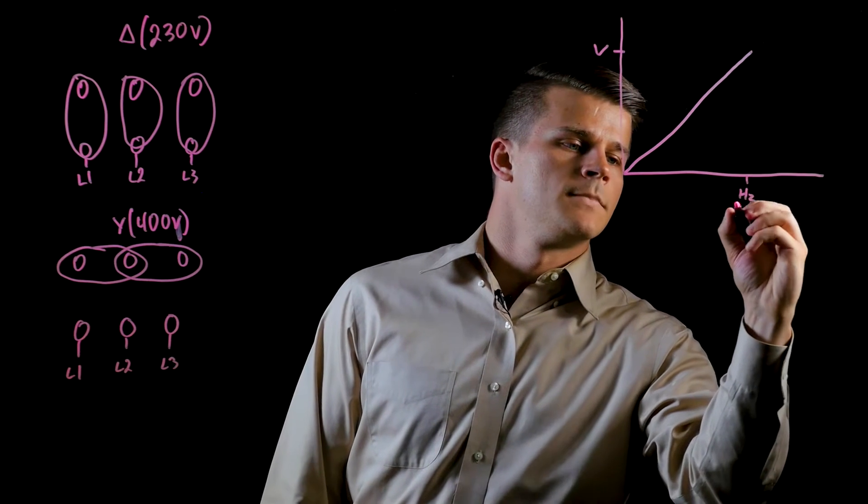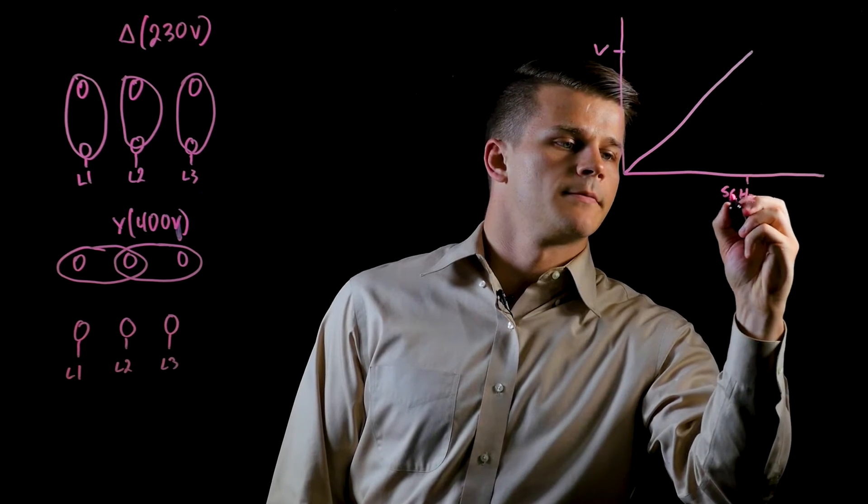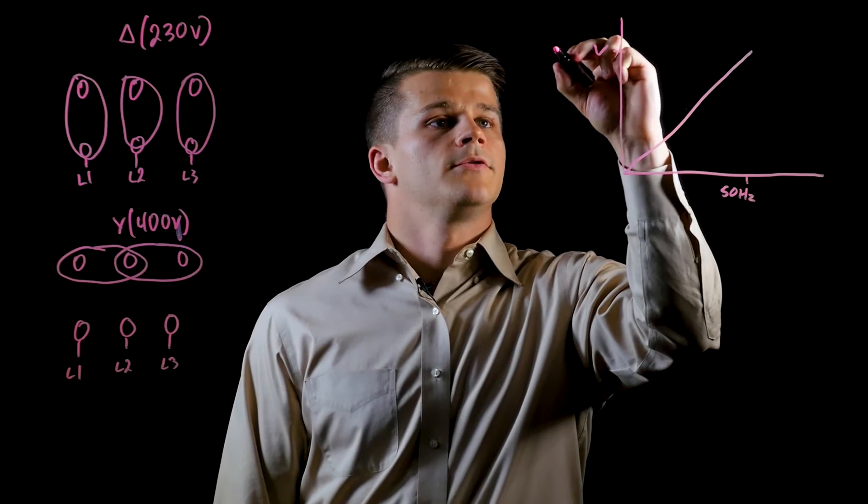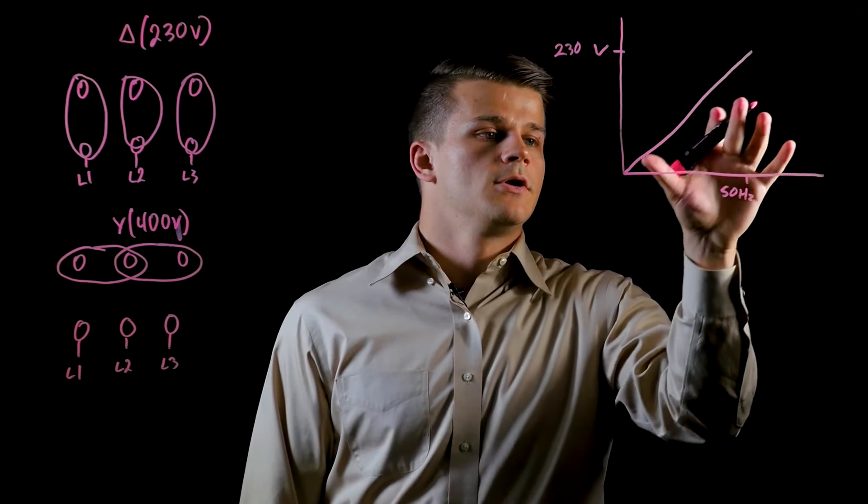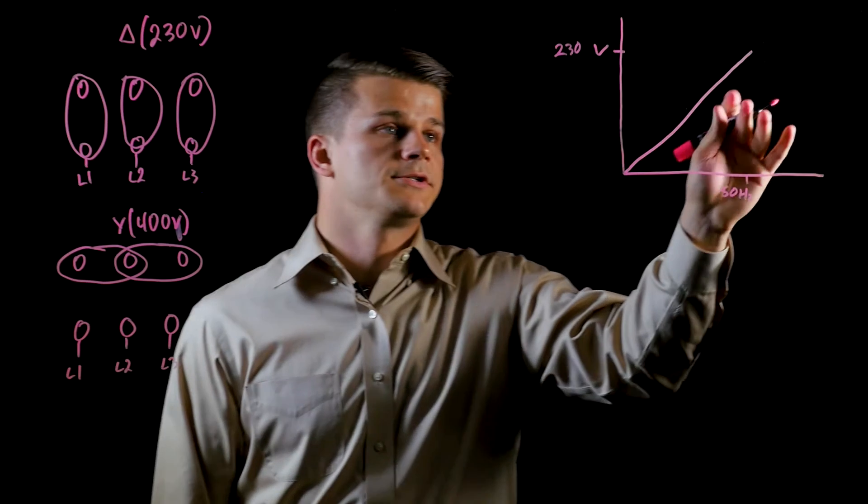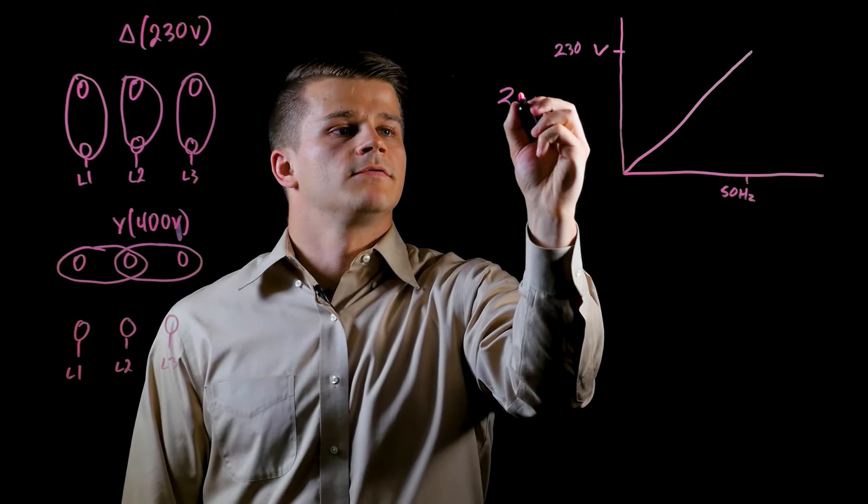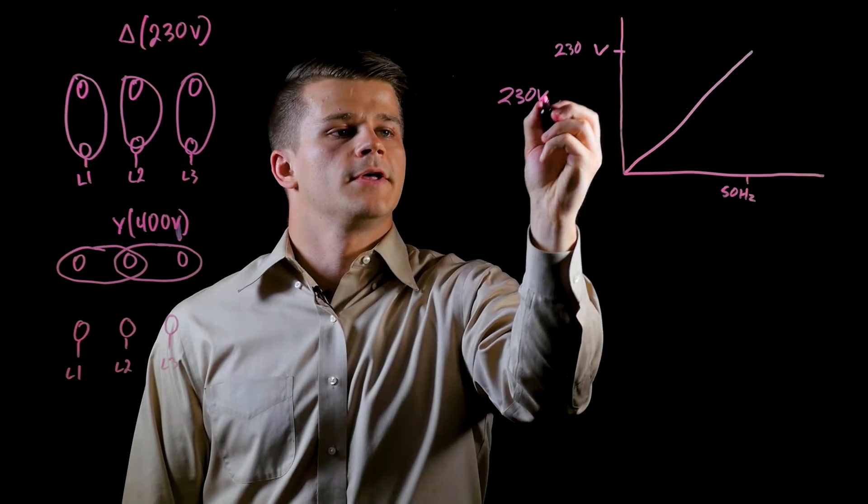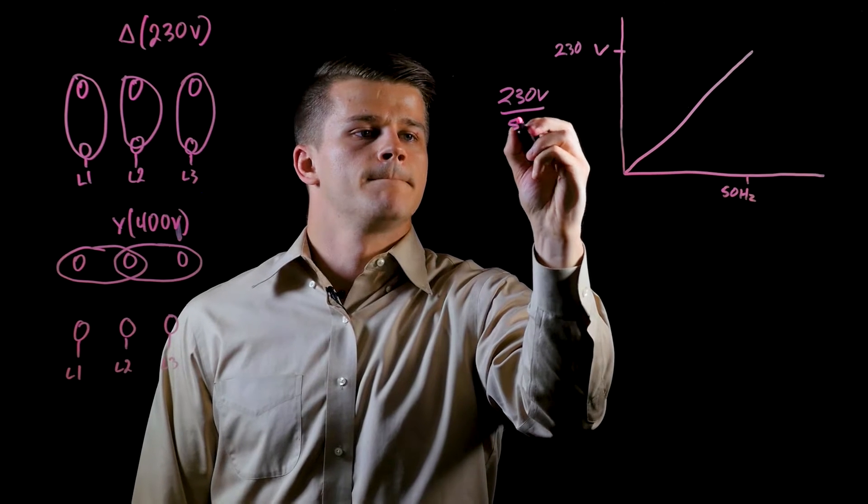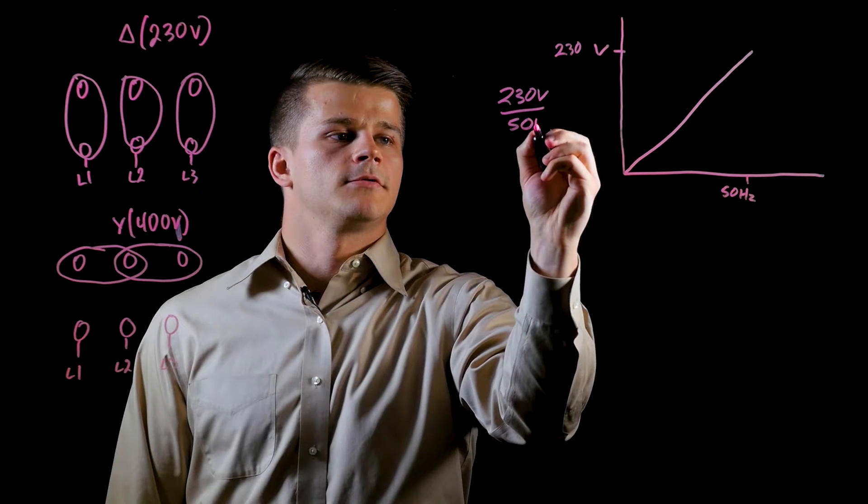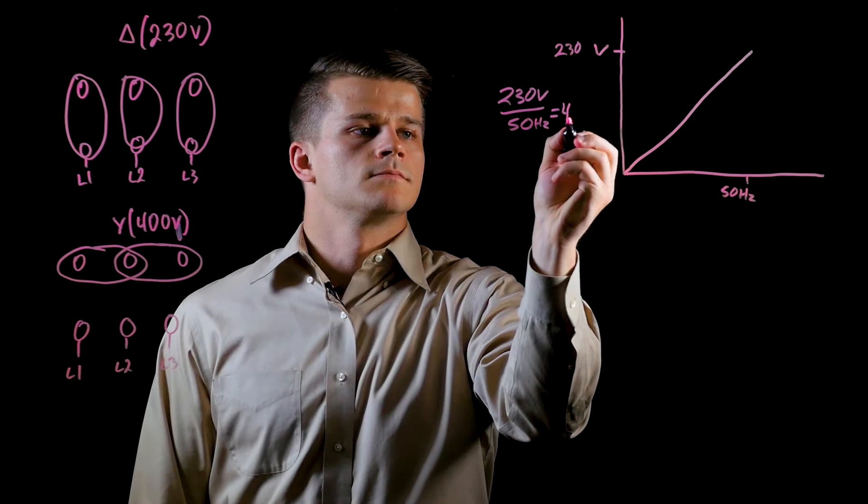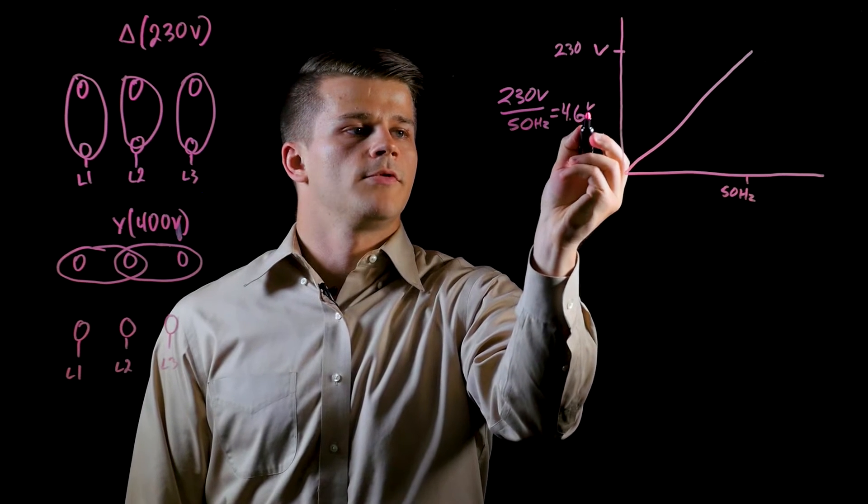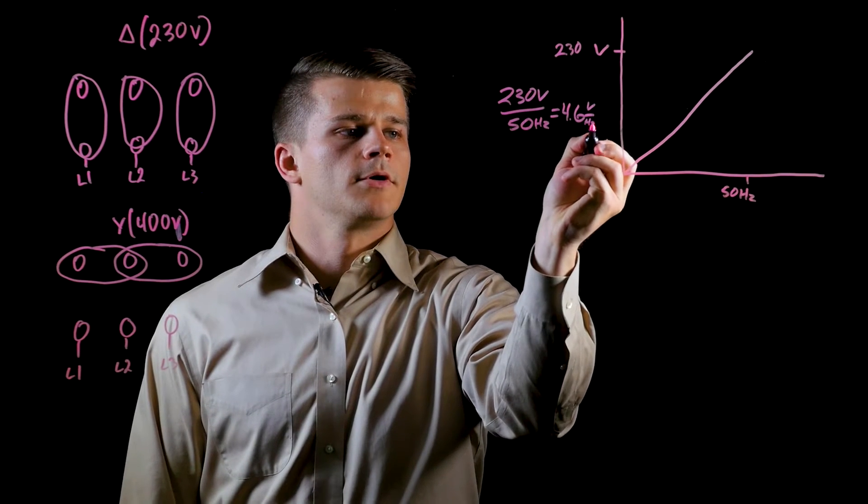Here at 50 Hertz and 230 volts for the Delta configuration, we have this linear relationship of voltage and frequency. If we do some quick math, we have 230 volts over 50 Hertz, which equals 4.6 volts per Hertz.